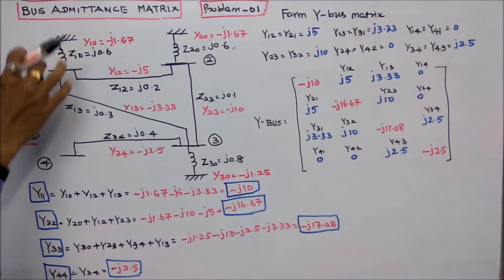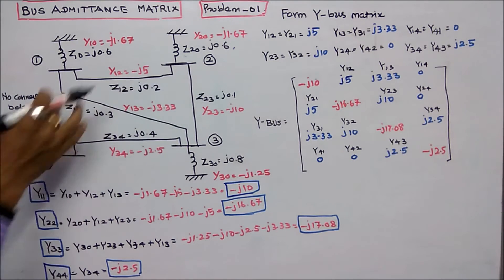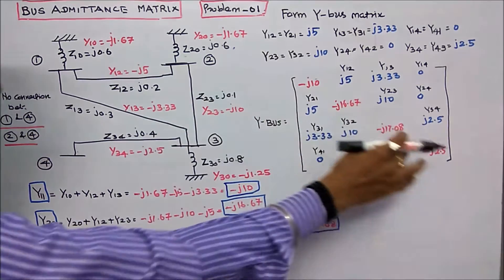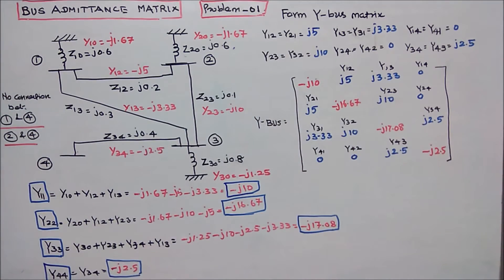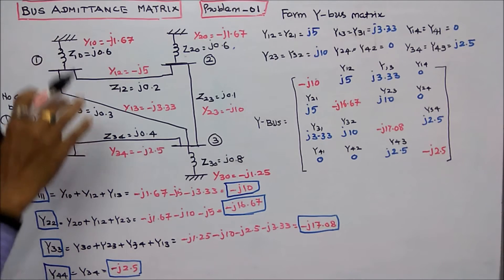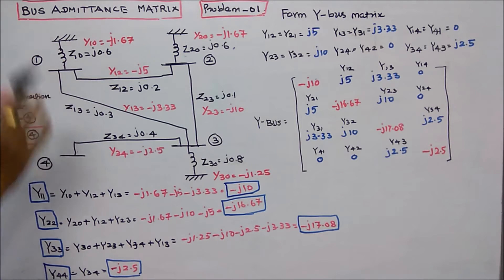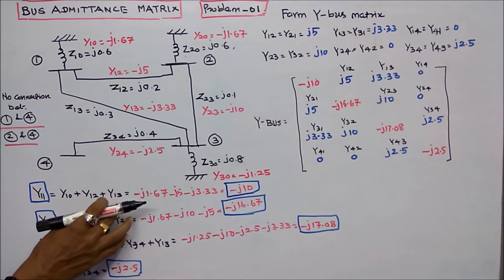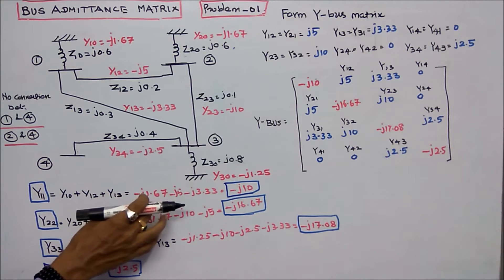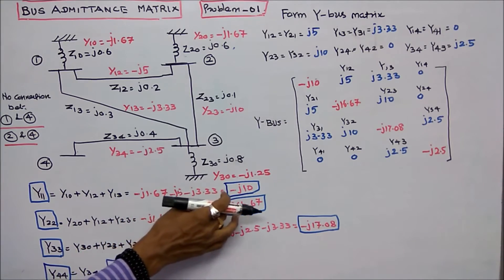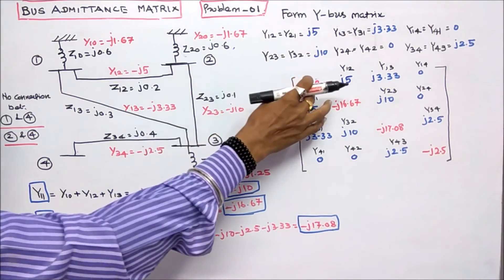There is no connection between buses 1 and 4, or between buses 2 and 4. First, we form the diagonal elements of the Y bus matrix. Y11 equals Y10 + Y12 + Y13, since three elements are connected to bus 1. That gives: −j1.67 − j5 − j3.33 = −j10.